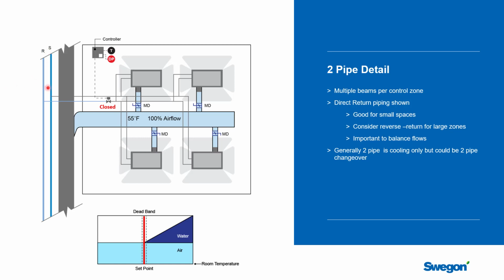And being a two-pipe system, we have a chilled water supply and return lines running around the building. And we're going to treat this as one control zone. So whatever happens to one beam, we're going to do to all of them. There's going to be one chilled water valve here that's run by this controller, and if the temperature climbs, we'll see that that valve will start to modulate to do that.